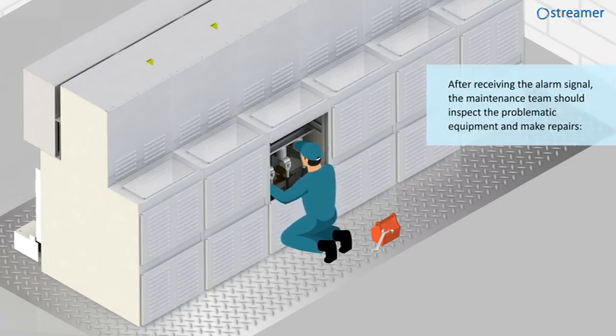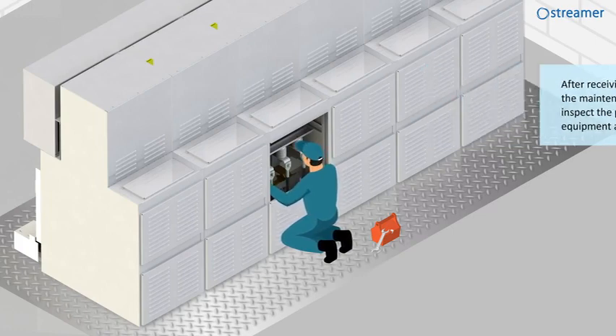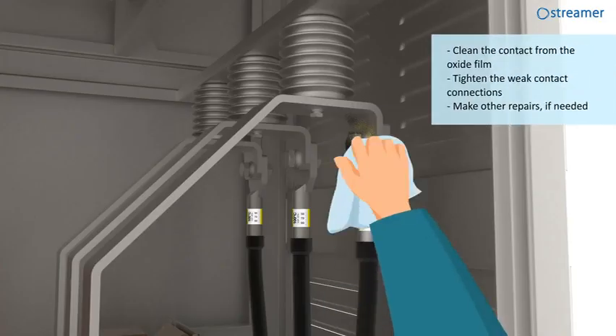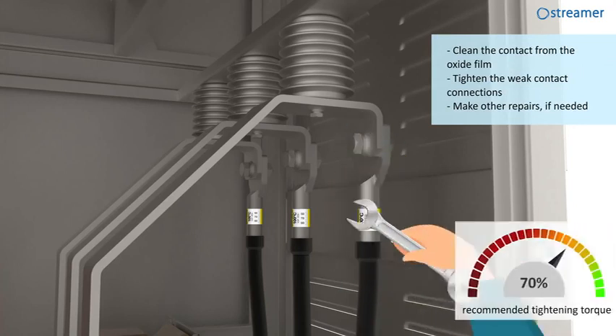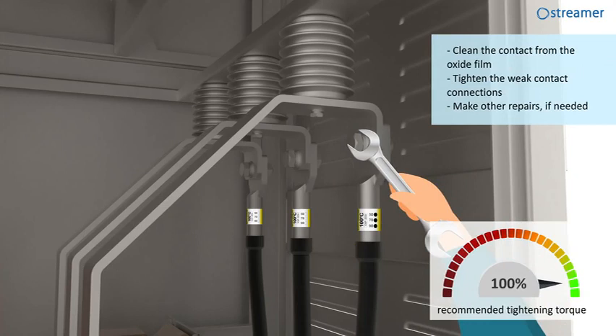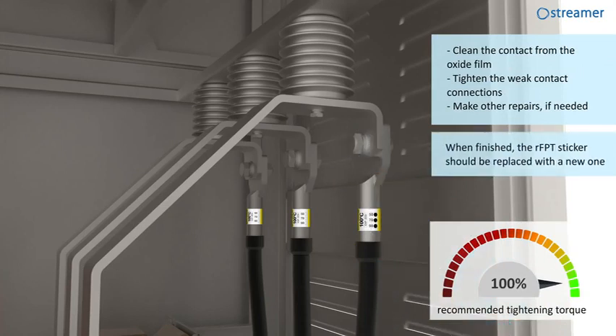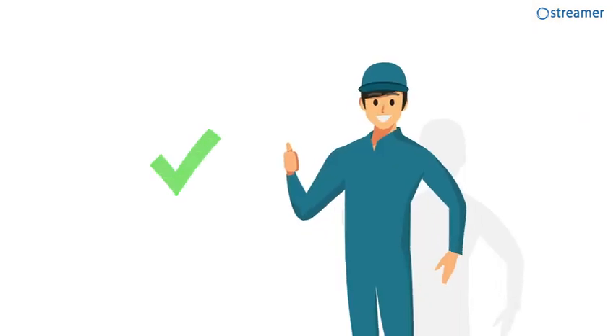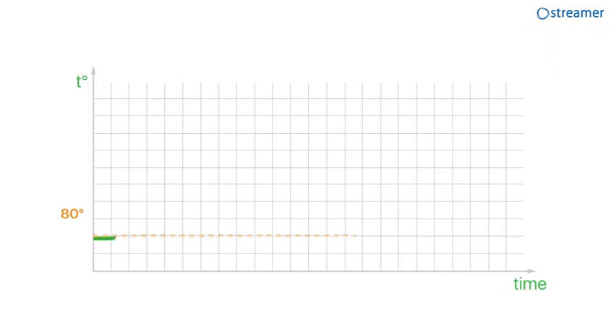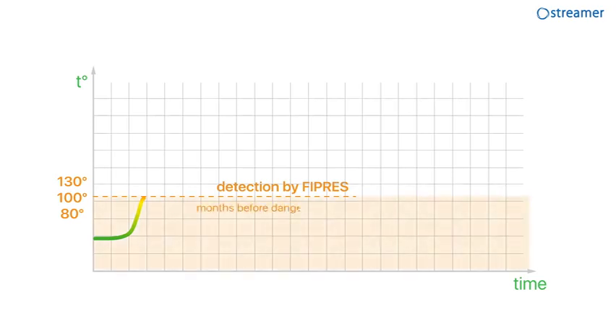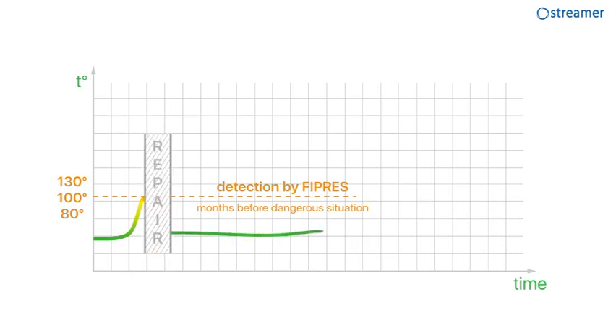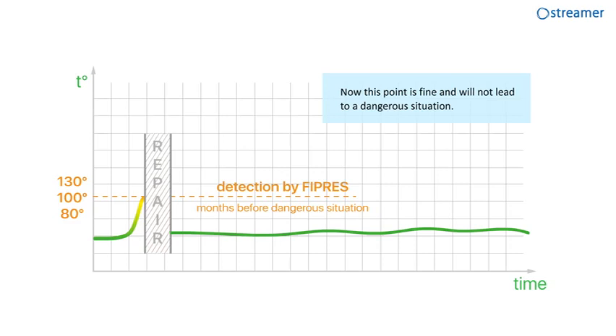After receiving the alarm signal, the maintenance team should inspect the problematic equipment and make repairs, clean the contact from the oxide film, tighten the weak contact connection, and make other repairs if needed. When finished, the RFPT sticker should be replaced with a new one. Now, this point is fine and will not lead to a dangerous situation in future.